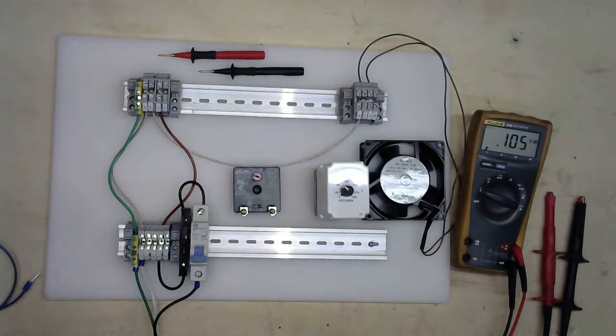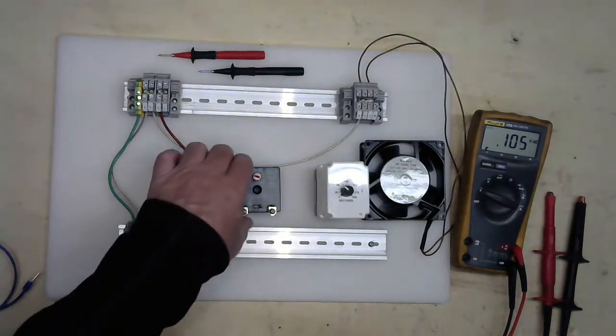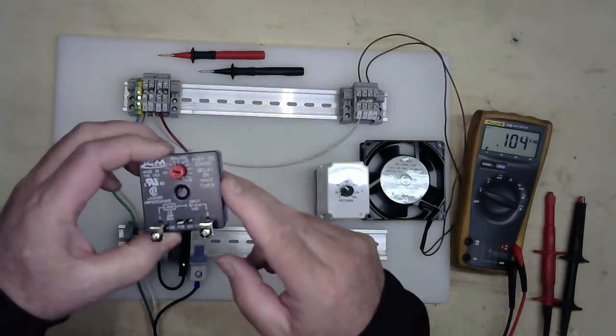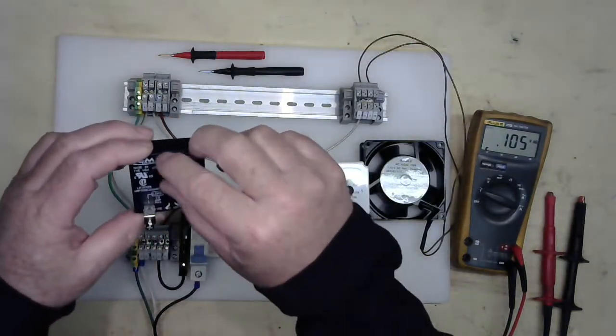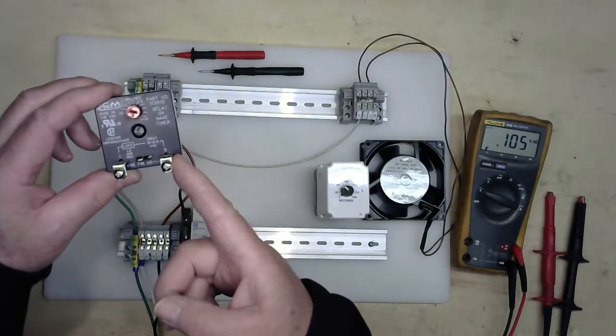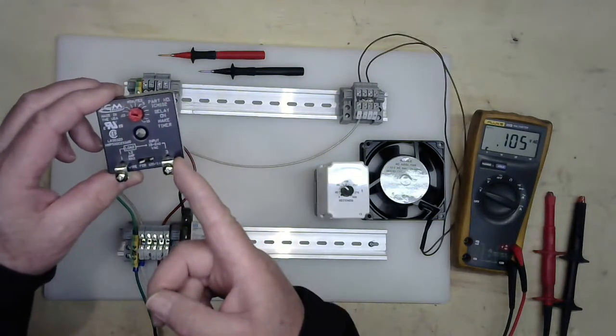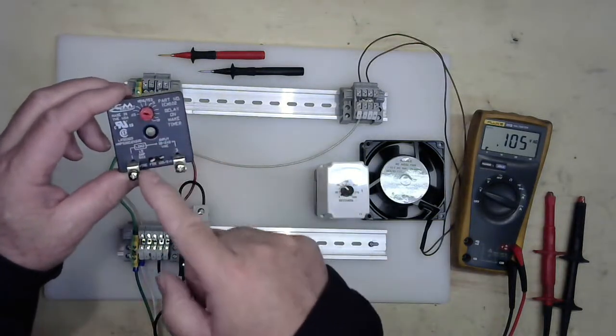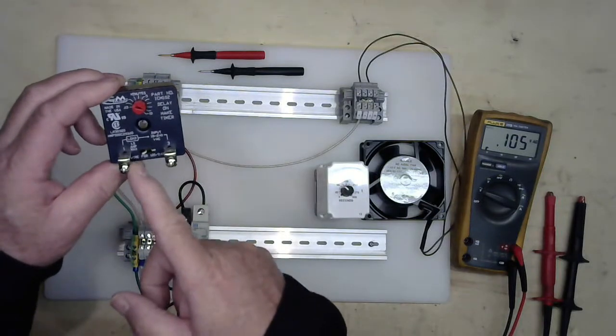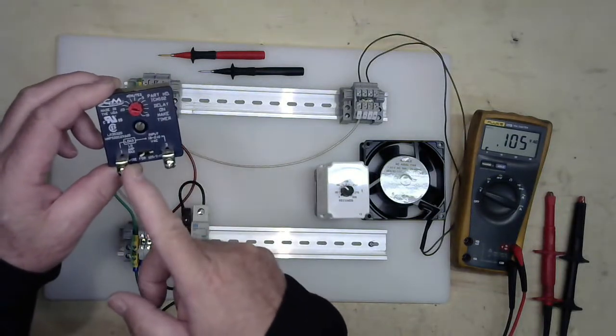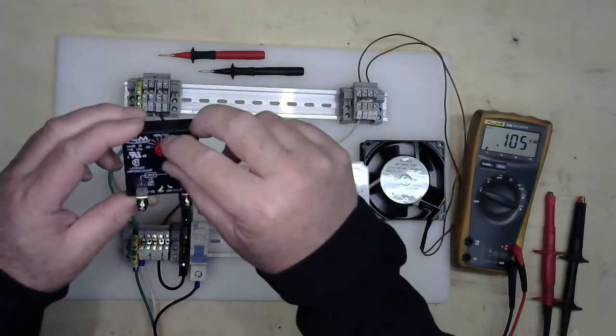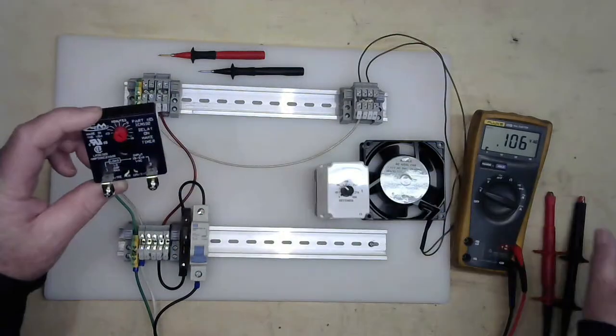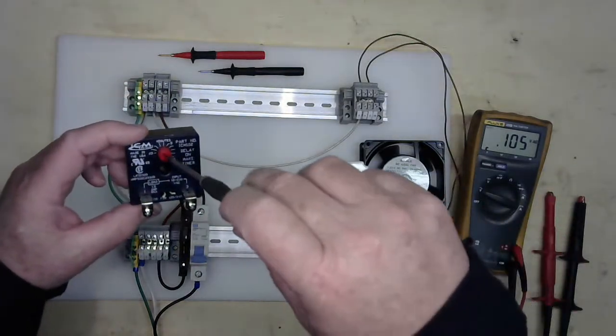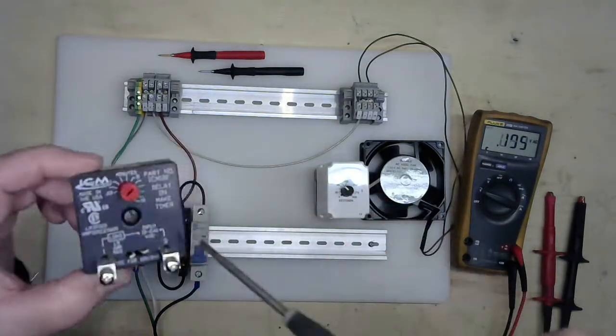Okay, today I'm going to talk about two different types of timers. I have a delay on make timer. This one's adjustable. You have your associated voltage going in. Once the timer times out, your load voltage will apply the same input power to your output load, signaling your load. This is adjustable, so you can adjust it to the timing that you want to set up.